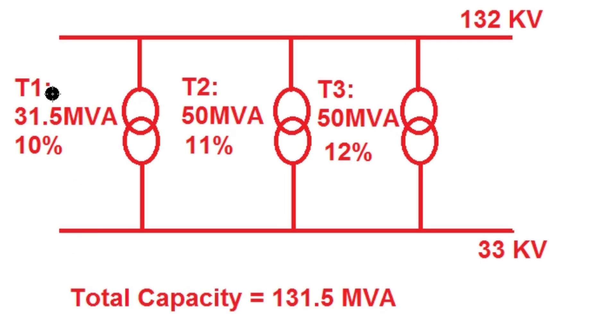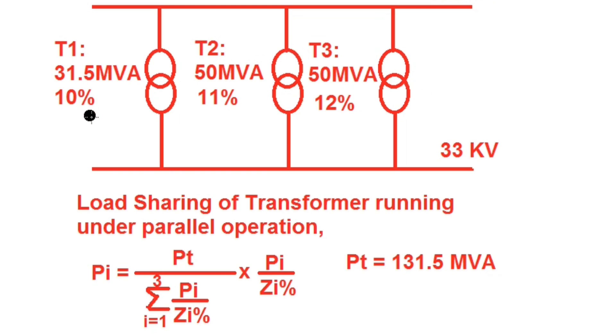The capacities of transformer 1, 2, and 3 are 31.5 MVA, 50 MVA, and 50 MVA respectively, giving a total substation capacity of 131.5 MVA. Under parallel operation, load sharing is governed by the capacity of each transformer in terms of MVA and their percentage impedance.